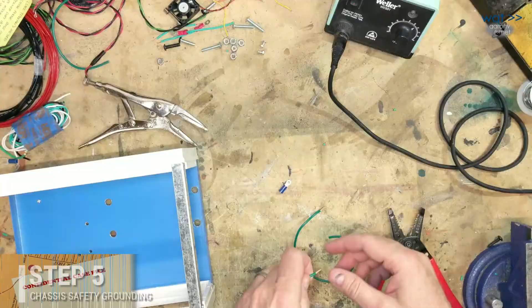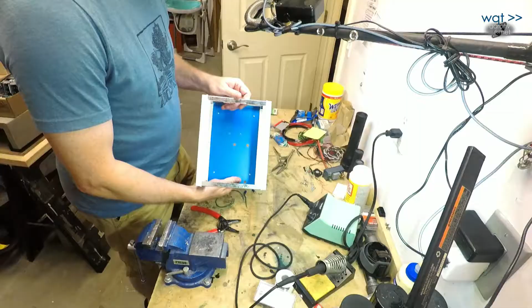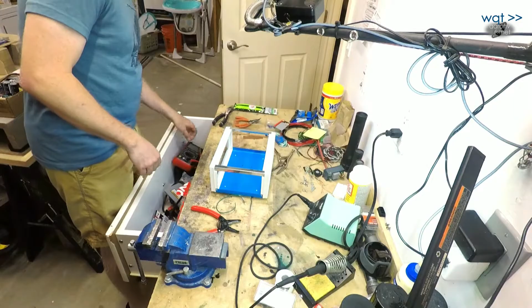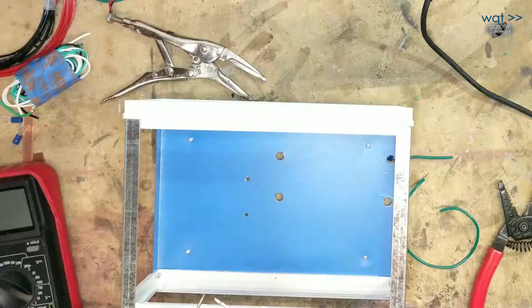Okay, the task of grounding this chassis is proving a little bit interesting. I've had to work through a couple ideas, and I think I've come up with something now. First off, I'm going to ground the base piece to the bar using a jumper exactly like the one I've got up in there. One thing I did have to do, which I've done over here also, was take a chisel and grind the extra powder coating out of that hole to make sure this screw makes a solid connection. But to prove that it does.